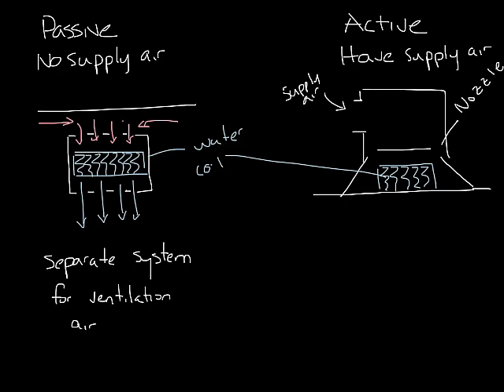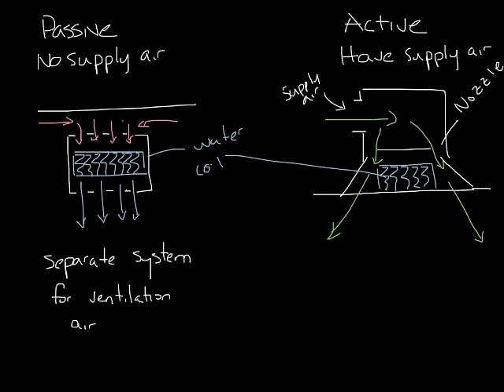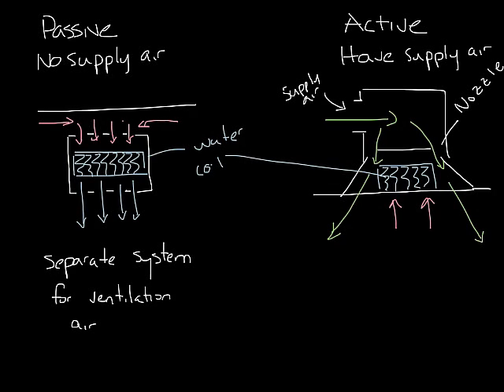So let's look at how this works. Your ventilation air will come in through the inlet, and it will go through the nozzles, and then out slots in the face of the diffuser. This will cause a low-pressure zone right in the center of the face of the diffuser, just under the water coil. Warm room air is pulled up over the coil, and it's cooled down. It is mixed with the ventilation air coming through the nozzles, and goes into the space to provide cooling.